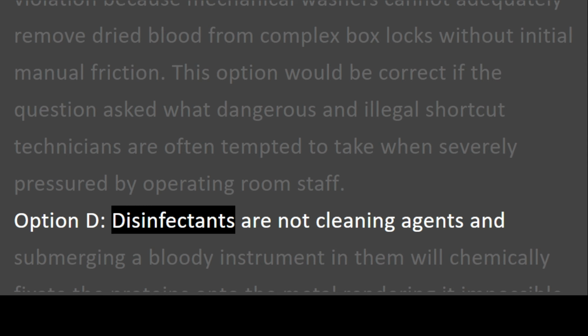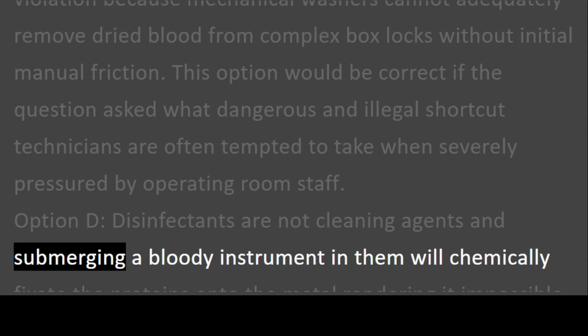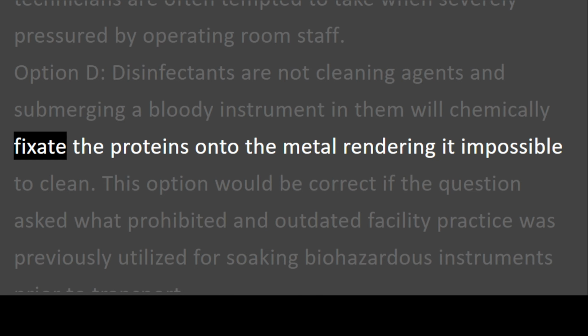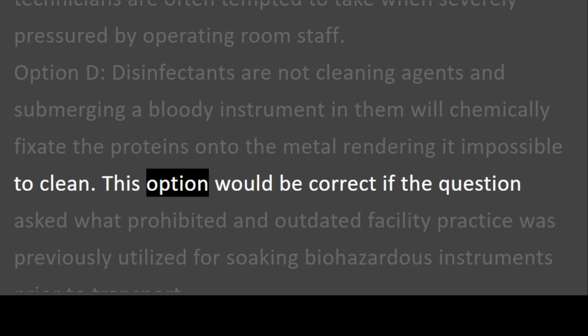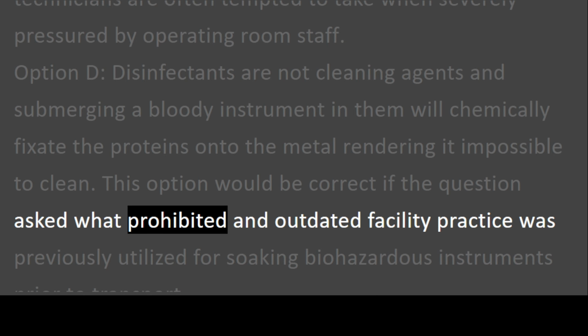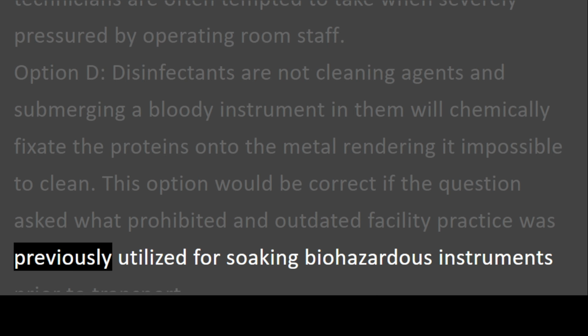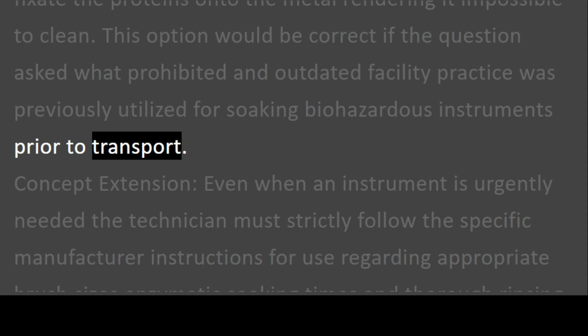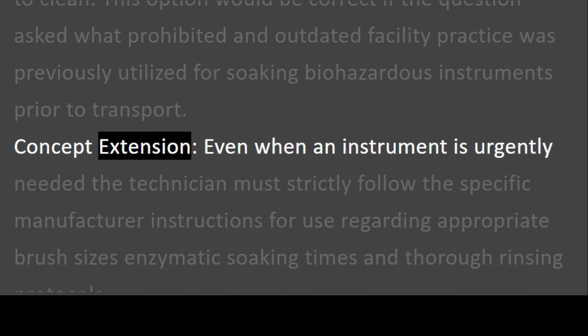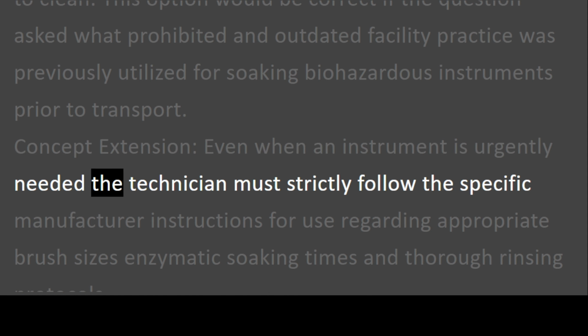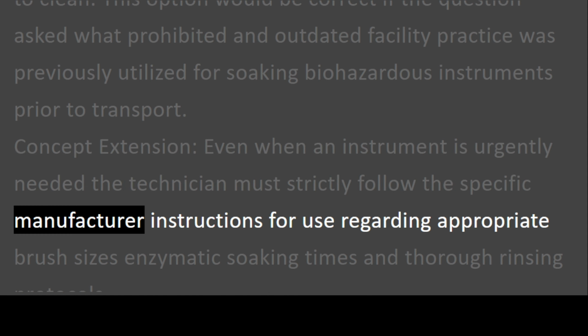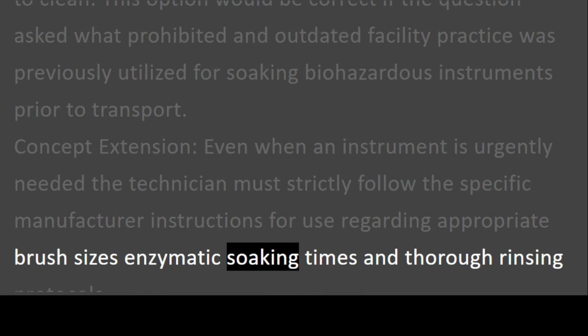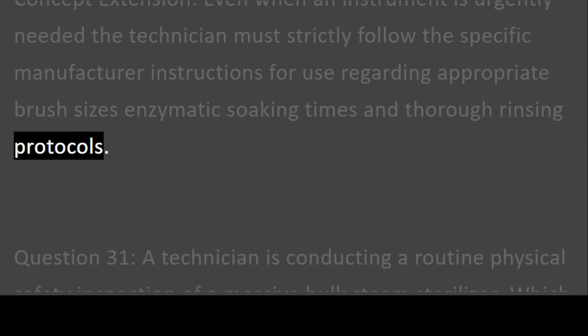Option D. Disinfectants are not cleaning agents, and submerging a bloody instrument in them will chemically fixate the proteins onto the metal, rendering it impossible to clean. This option would be correct if the question asked what prohibited and outdated facility practice was previously utilized for soaking biohazardous instruments prior to transport. Concept extension. Even when an instrument is urgently needed, the technician must strictly follow the specific manufacturer instructions for use regarding appropriate brush sizes, enzymatic soaking times, and thorough rinsing protocols.